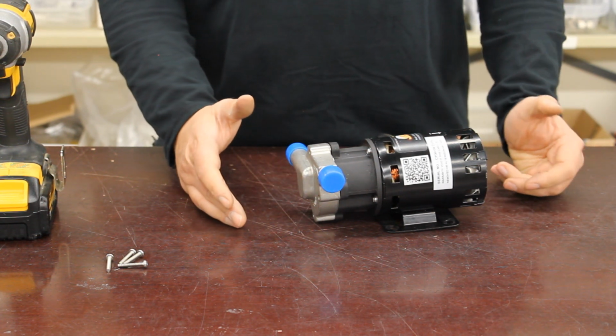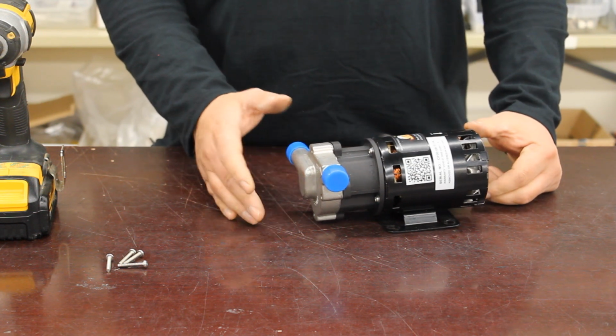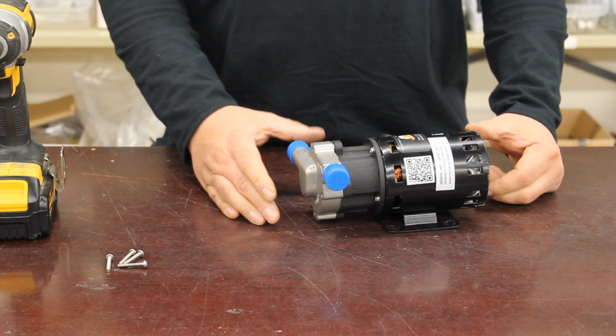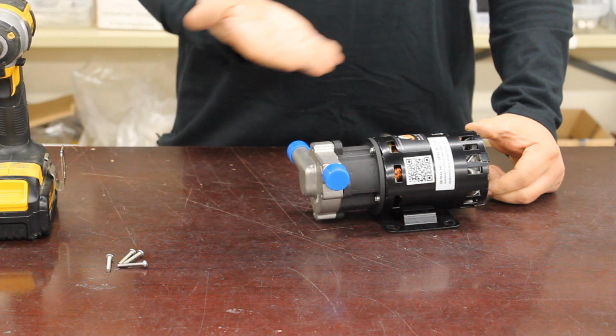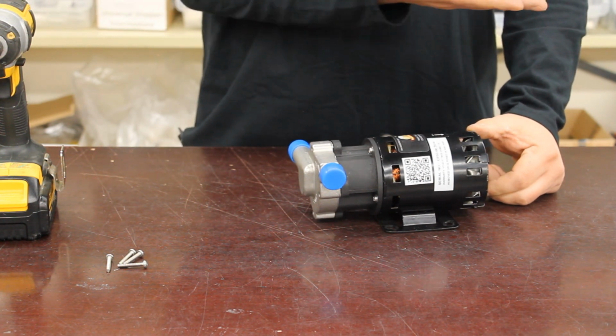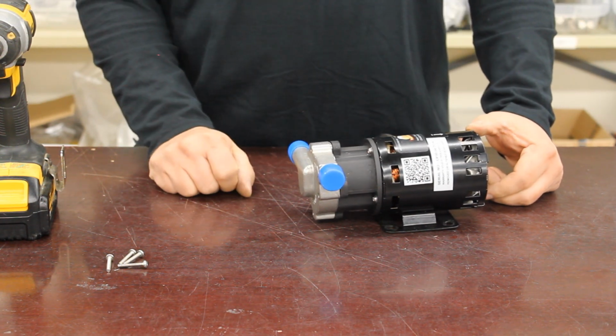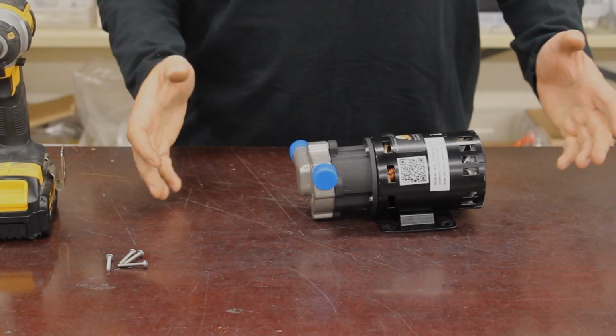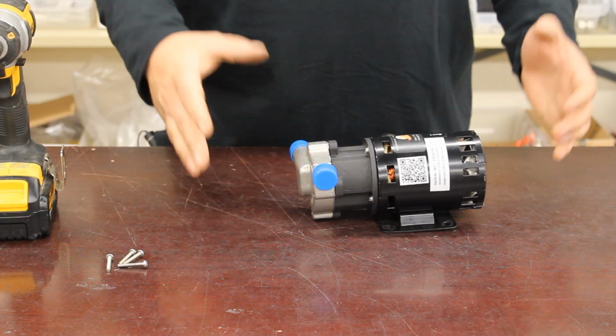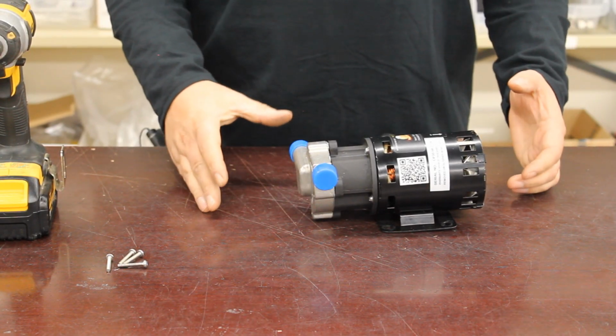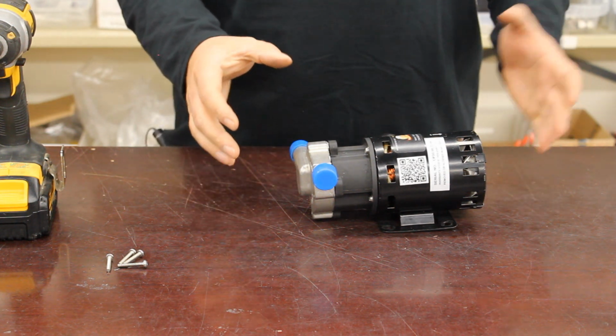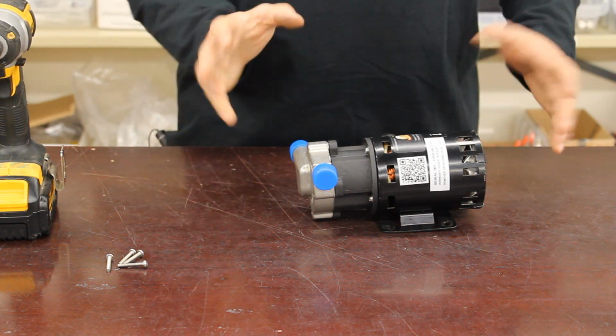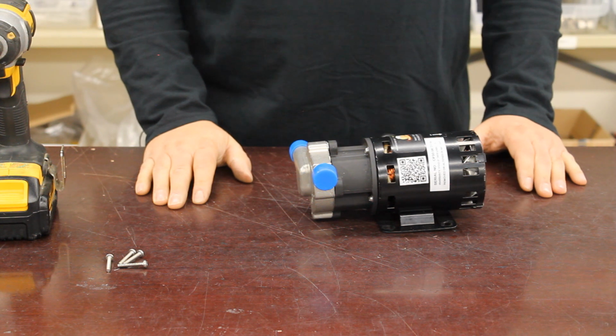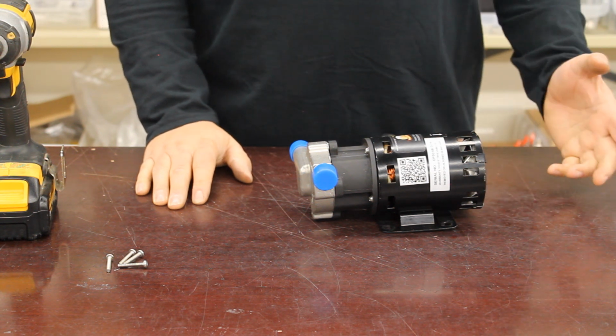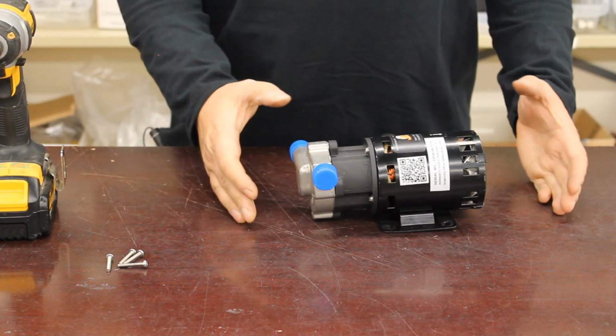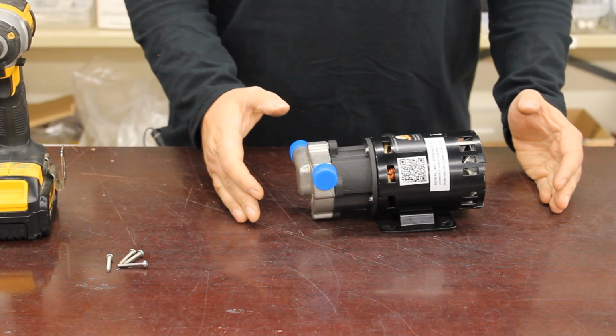Either reposition the pump somewhere else, much lower or further away from the burner, or install a heat shield underneath your burner so that all of that heat does not come down onto the motor. Along the same lines, we've seen customers install these pumps inside toolboxes to put switches and controllers, and conceivably to keep water off of the pumps. Again, same problem. These pumps are not meant to be installed in enclosed spaces.